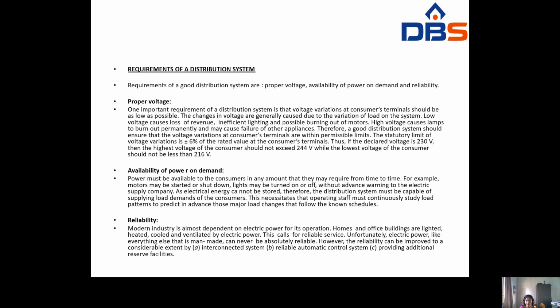Suppose high voltage occurs, at that time the voltage will not exceed 244 volts. If the voltage is reduced at the consumer's point of view, at that time it should not be less than 216 volts. So this is one of the requirements of a distribution system.